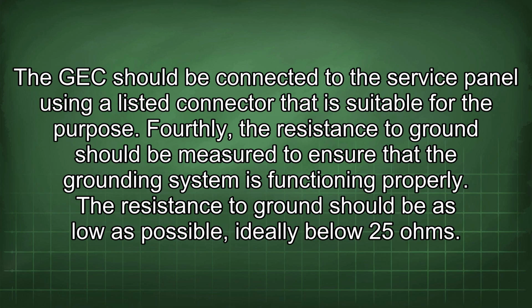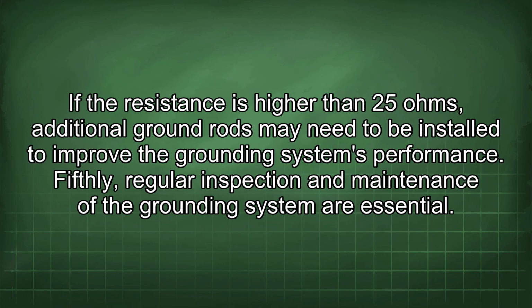Fourthly, the resistance to ground should be measured to ensure that the grounding system is functioning properly. The resistance to ground should be as low as possible, ideally below 25 ohms. If the resistance is higher than 25 ohms, additional ground rods may need to be installed to improve the grounding system's performance. Fifthly, regular inspection and maintenance of the grounding system are essential.